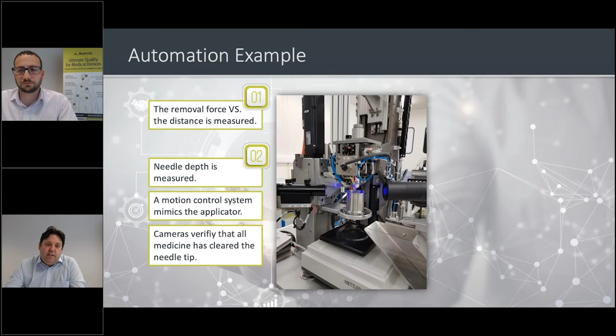The RFID tag is then marked on the insert as used for testing. By having these tasks performed together on the same station, we are able to perform an exact simulation of the reusable applicator while gathering highly accurate measurements in a continuous process. All the data is automatically logged and easily tracked back. The results are consistent and completely reliable for both patient safety and comfort.